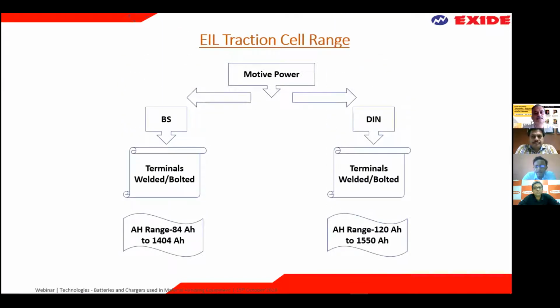Now, in India, for motive power applications, there are two major dimensional standards followed for traction batteries: BS, the British standard, and the DIN standard. For DIN standard in India, there are two different types of cells used: one is the welded type, where the terminals are welded to each other, and the other is the bolted terminal type, where you connect each cell with a connector, either a copper connector or a flexible connector. For the BS range, the usual ampere hour range for batteries is from 84 ampere hour to 1404 ampere hour, and for the DIN range, it's 120 ampere hour to 1550 ampere hour.